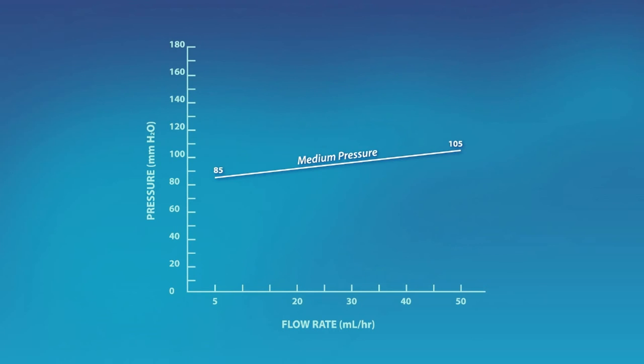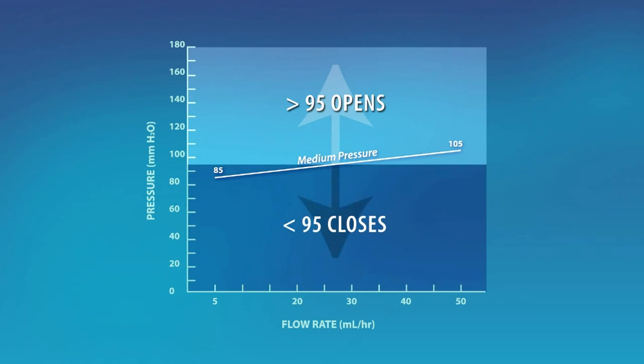For example, if a surgeon is using a medium pressure valve and an average flow rate of 25 milliliters per hour, the valve will have a nominal resistance of 95 millimeters H2O. Therefore, when the ICP is above 95 millimeters H2O, the valve opens and drains. When the ICP is lower than 95 millimeters H2O, the valve closes.